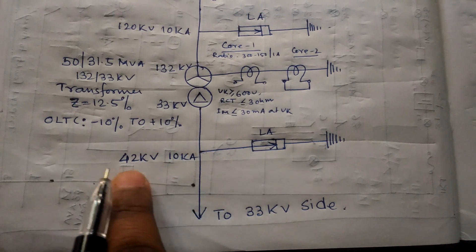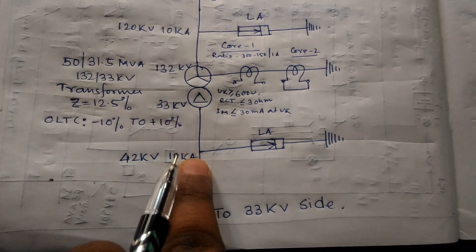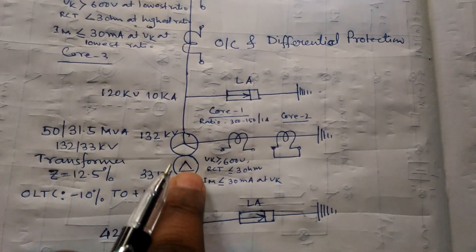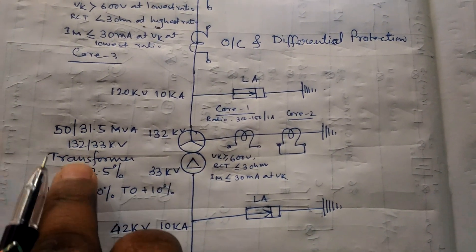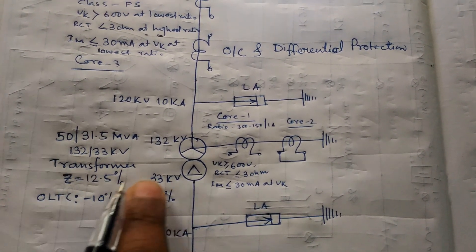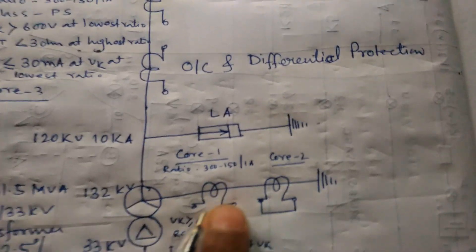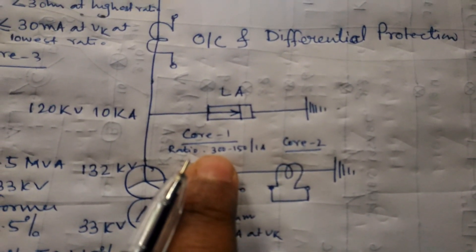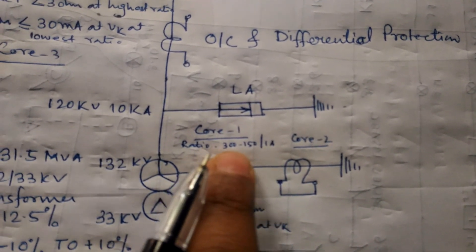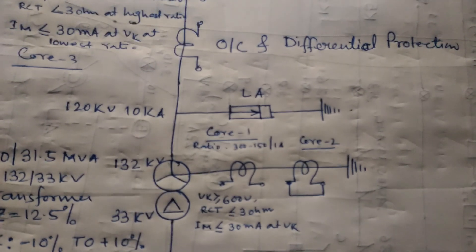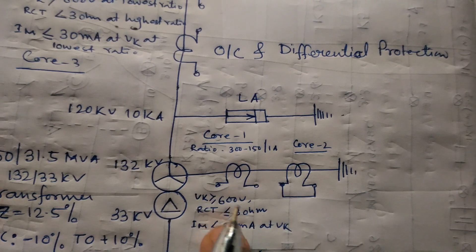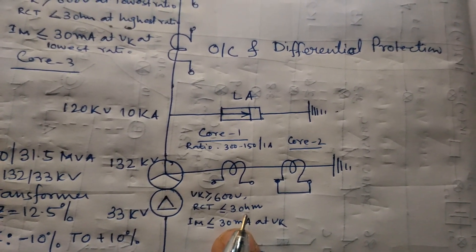On the 132 kV side, 120 kV 10 kA lightning arrestors are used. On the 33 kV side, 42 kV 10 kA lightning arrestors are used. The transformer discussed here is 50 MVA, 132/33 kV, with impedance of 12.5%. The neutral CT used here has the same ratio — 300/150/1 — with 2 cores: one core is shorted and one core is used for REF protection.